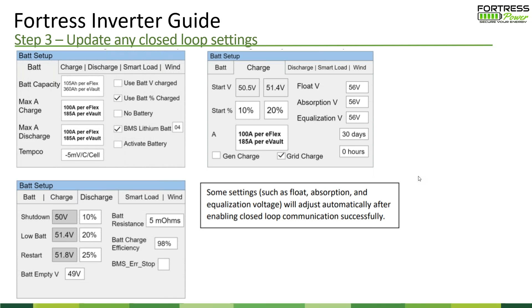And when you look at the voltage levels, you look at that voltage discharge curve. It's very easy to know when the battery's empty based off voltage. It's very easy to know when the battery's full based off voltage. It's that middle range that becomes the blind spot in terms of voltage-based controls. So by enabling percentage-based controls, you can more readily step down the inverter based on sellback parameters, so that if you don't need to aggressively dump the entire battery in a matter of 2 hours, but your time of use rate is a period of, say, 4 or 5 hours, you can more casually discharge the battery and get a longer life out of it accordingly, based on stepping it down on the various percentage levels.